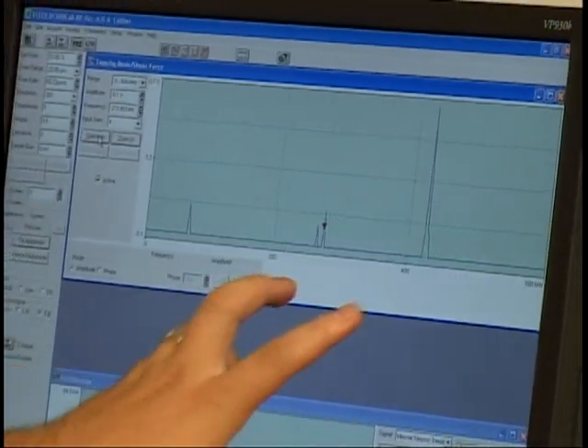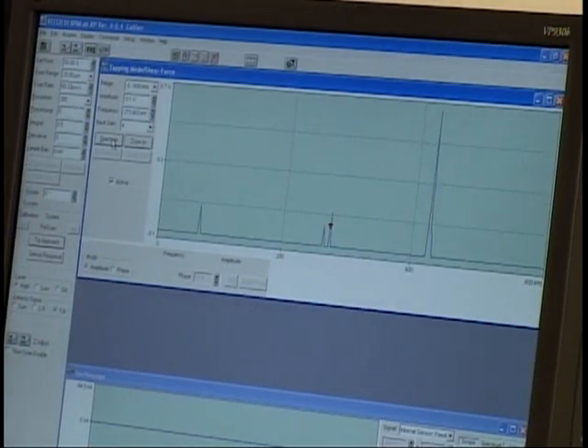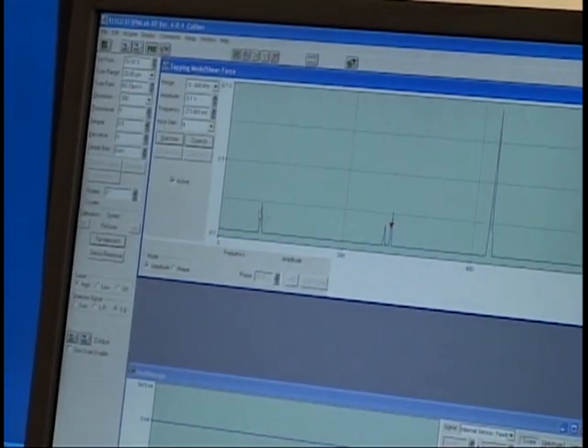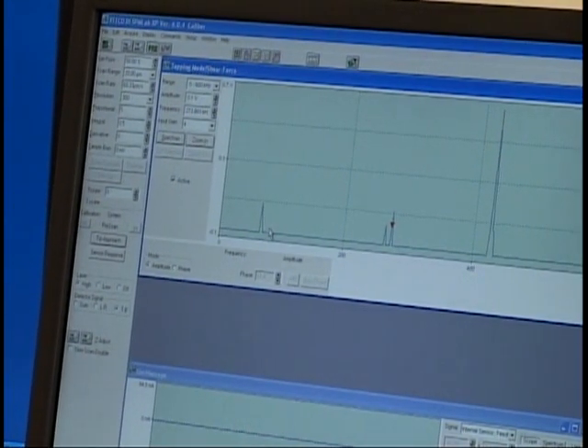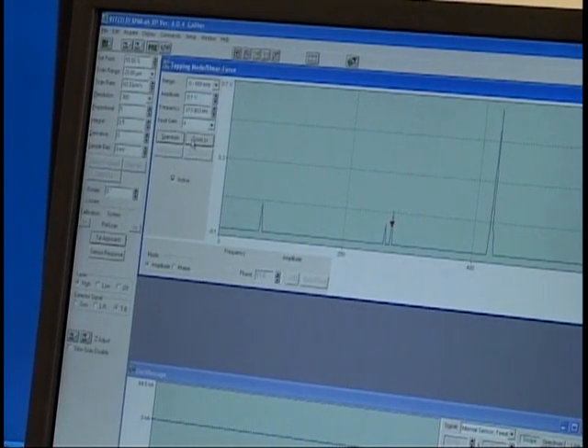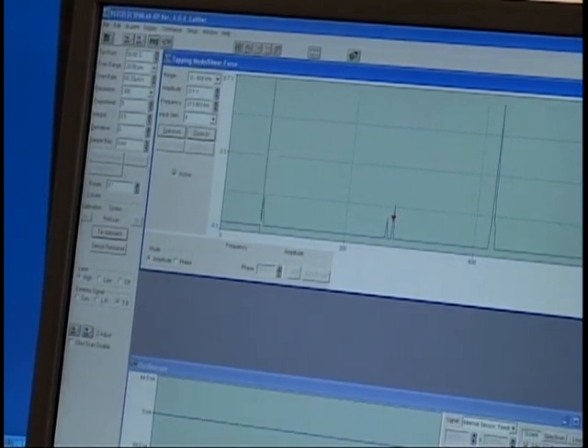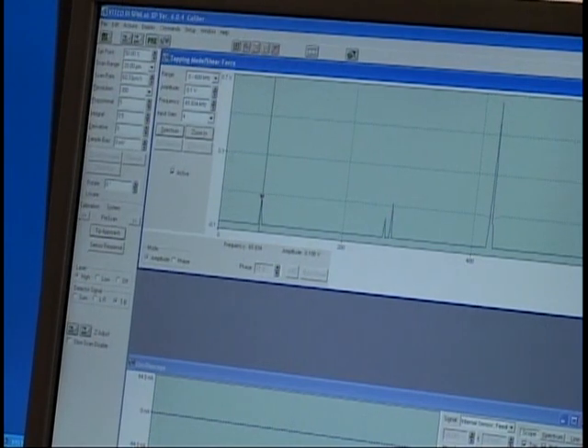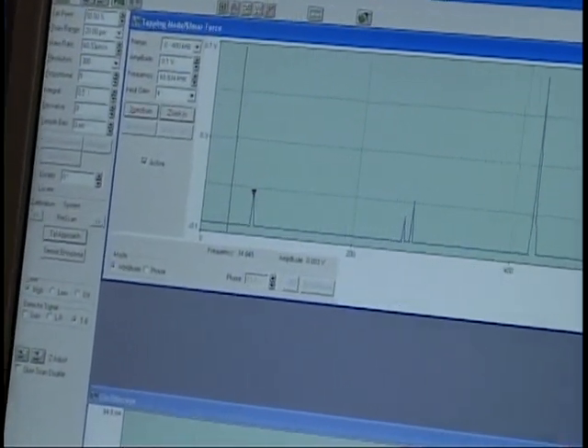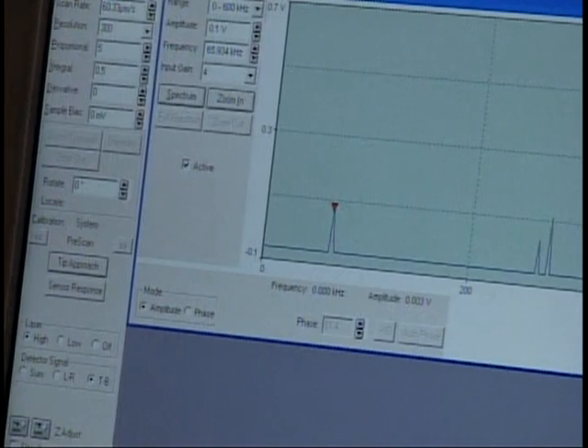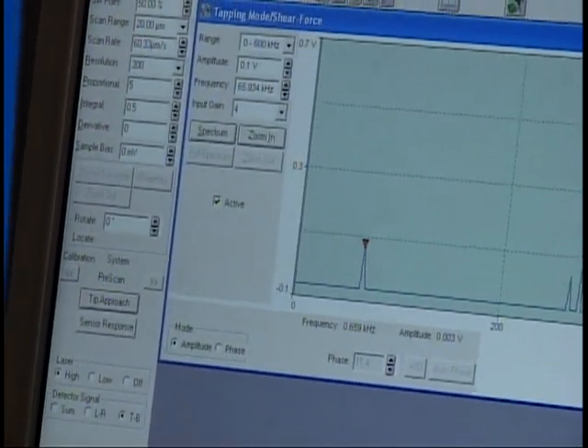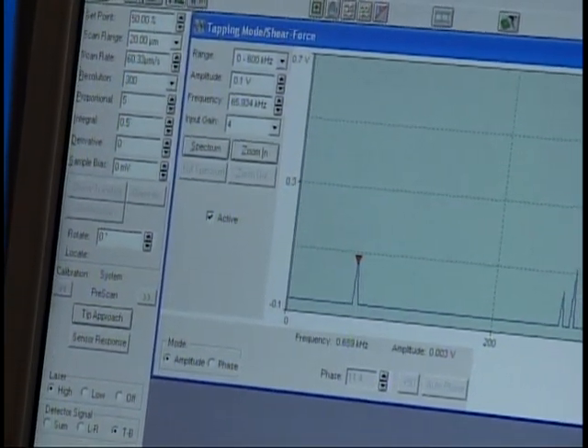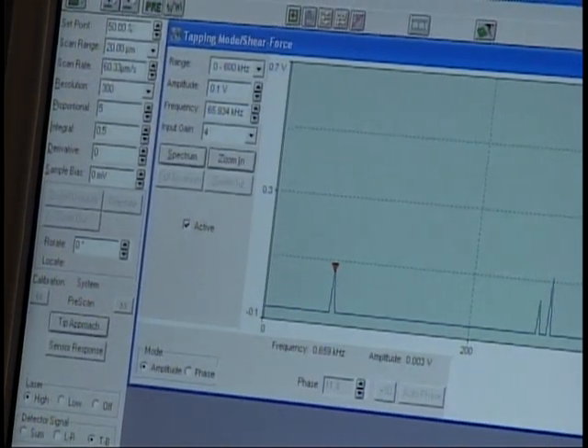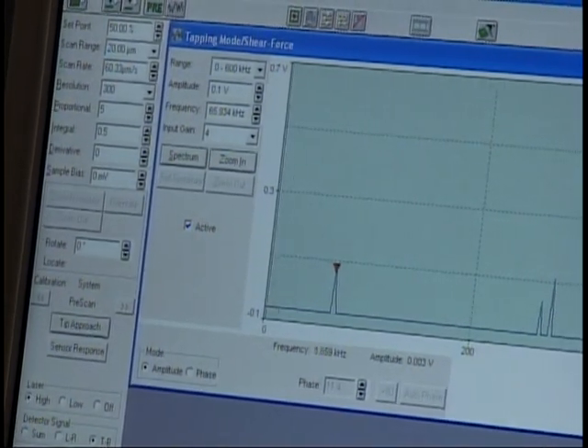Most likely these 2 are harmonics of the first one. So your natural frequency is the first one. So let's zoom in on it and see if it improves. Because right now we're looking at 0.1 volts of amplitude. Ideally we want an amplitude reading of 5 volts. 4.5 to 5.5 volts is a good range to have for an amplitude on your peaks.